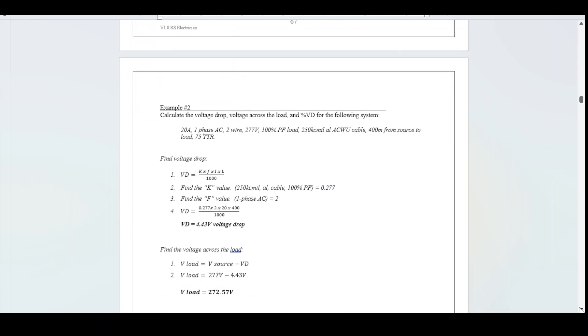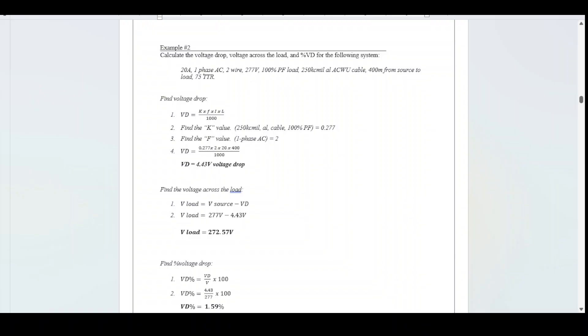Example number 2: calculate the voltage drop, voltage across the load, and percent voltage drop for the following system. 20 amps, single-phase AC, 2-wire, 277 V, 100% power factor, 250 kcmil aluminum, ACWU cable, 400 meters from source to load, 75-degree termination temperature. K-value is 0.277; F-value is 2. Voltage drop equals 4.43 V. Voltage across load equals 272.57 V. Percent voltage drop equals 4.43 divided by 277 times 100, giving 1.59%.